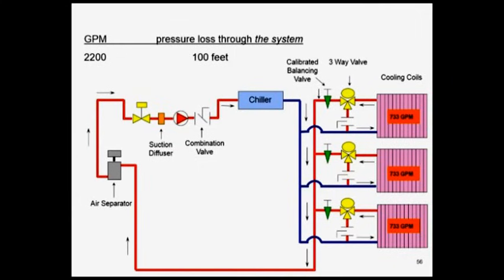And we know in this particular case that our flow rate was going to be 2,200 GPM and the pressure drop 100 feet of head. So now we know from design, the engineer calculated a pressure drop through the critical loop here. He calculated the three-way valve, the cooling coil, the return piping, the air separator, the suction diffuser, service valves, the chiller, everything. A detailed loss calculation. He came up with 100 feet of pressure drop at 2,200 GPM. That's what he specified his pump for. That's what the pump was purchased to do: 2,200 GPM at 100 feet of head.